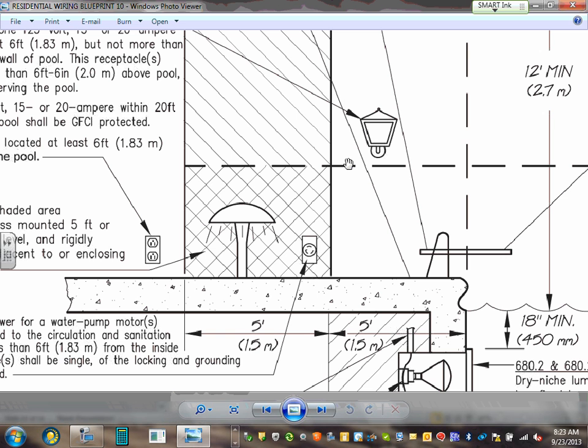Okay, now, just a little bit, we're not doing storable pools, guys. If you have a storable pool, almost the same rules. You have to have one GFCI receptacle, not closer than 6 feet and not further than 20 feet. Any receptacle within a 20 feet radius of a storable pool or a permanent pool has to be GFCI'd. The pump for a storable pool or a permanent pool that runs between 120 and 240, 15 and 20 amp, has to be GFCI. Same rule for both of them.